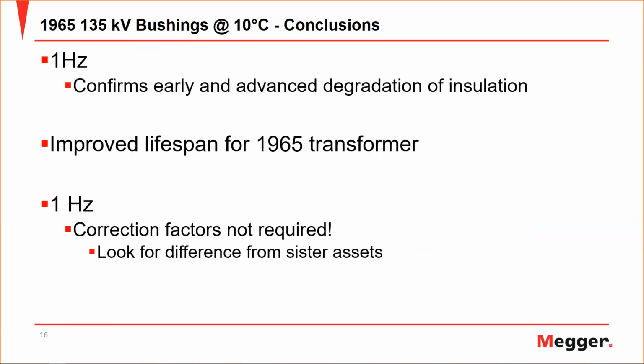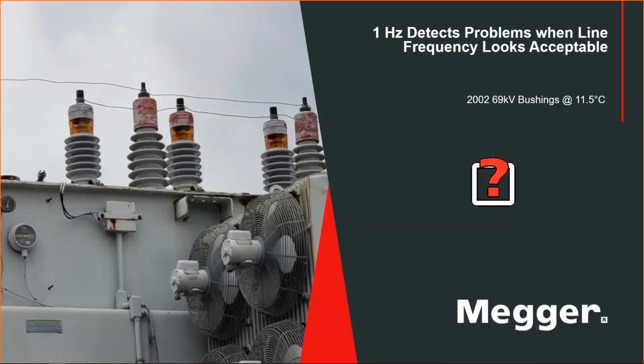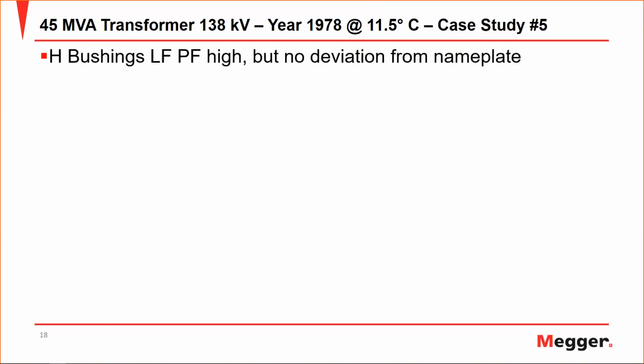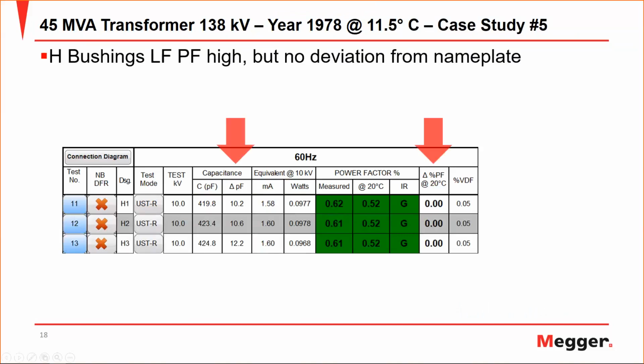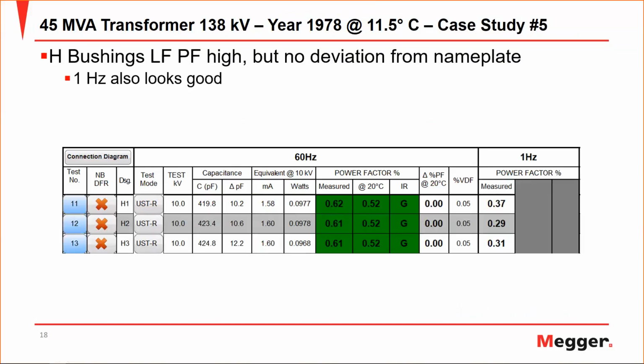And this is perhaps the easiest way of thinking when looking at bushings: just compare the values from their sister bushings, and most of the time you can notice differences early on when looking at 1 Hertz. But now I want to move on to looking at bushings and detecting problems when line frequency looks acceptable. This will be the same example from the transformer that I just discussed earlier, where confirming that 1 Hertz can show that a bushing is in good condition.